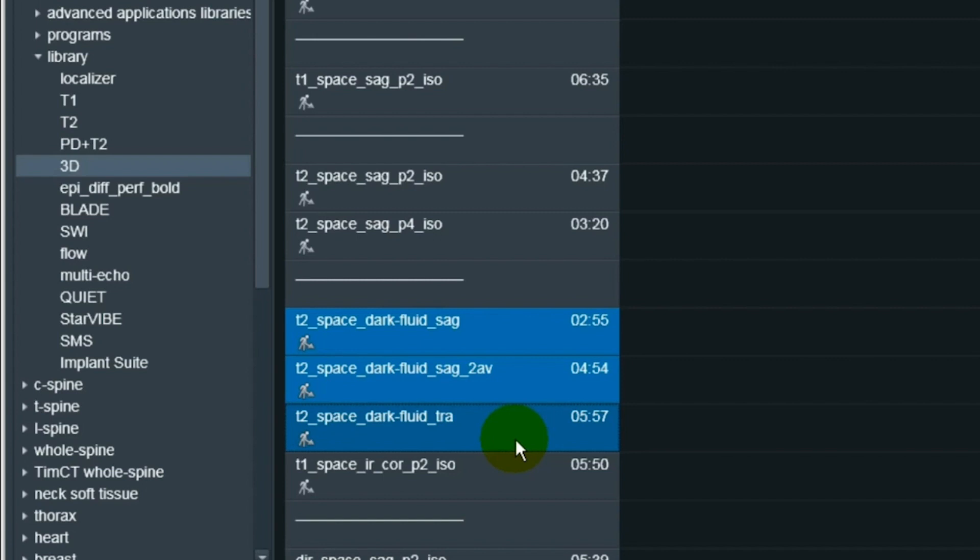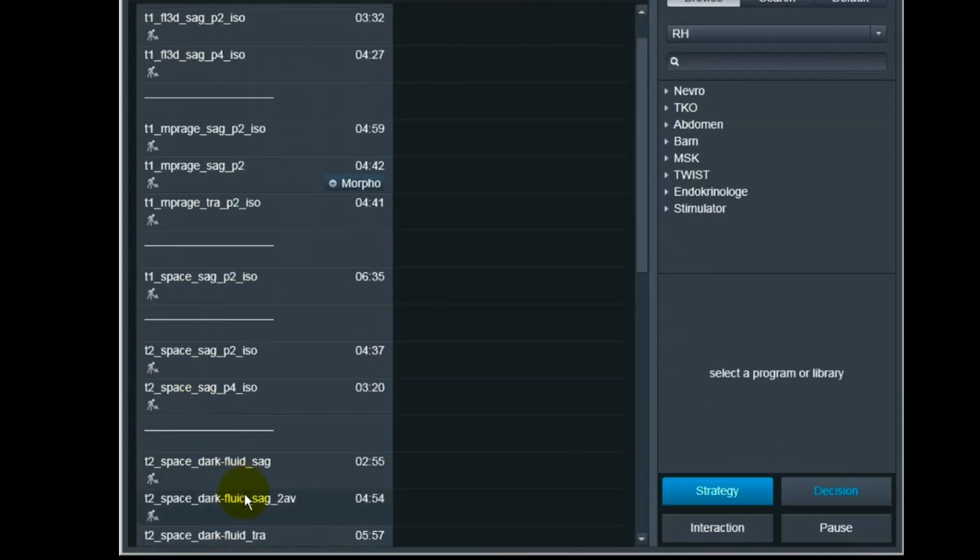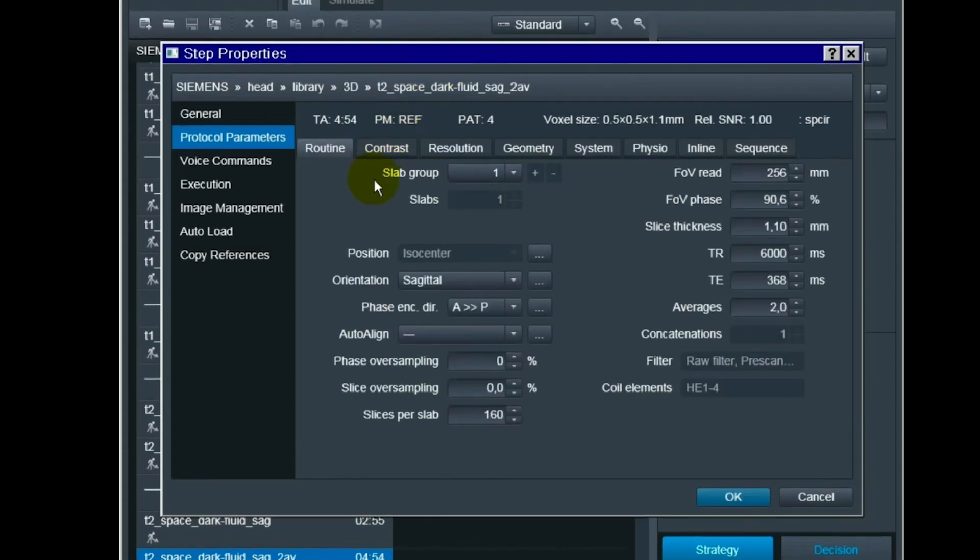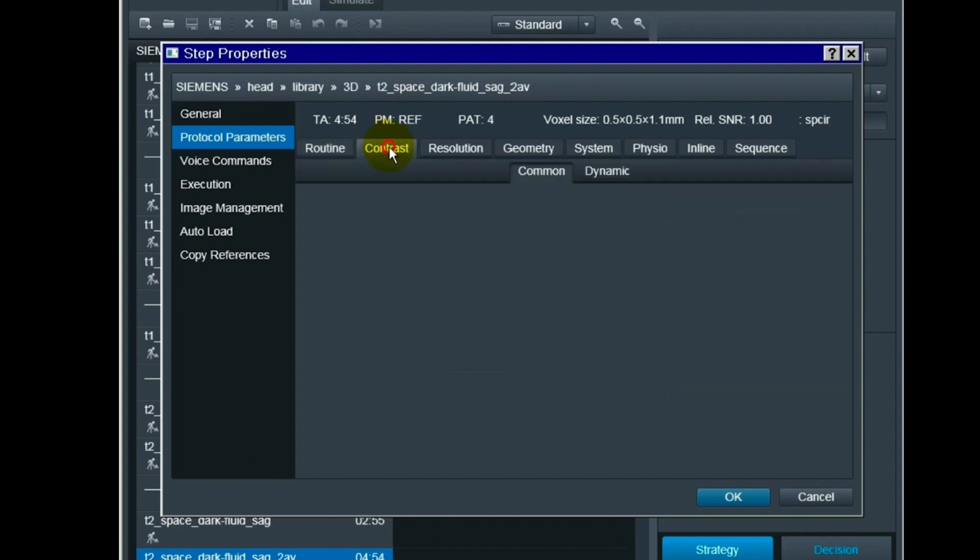Let's go inside one of them and check it. Let's go to edit mode, scroll down to the FLAIR. Okay, so 2 AV, that means two averages, right, as seen right there. Another thing I notice is that right here, look at the TR. The TR now as a standard is much higher than it used to be on older software where we used to be 5000, but now it's 6000.